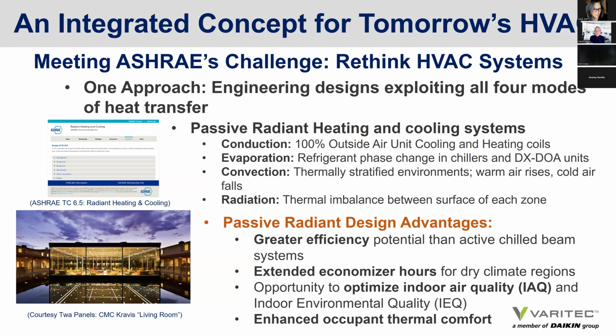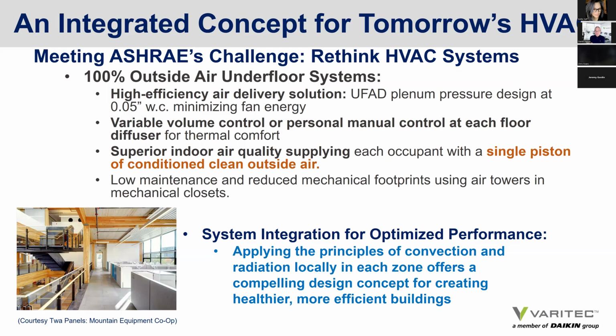Also to look at 100% outside air passive radiant systems because of outside air delivery solutions being more efficient for reasons expressed. Variable air volume control or personal manual control is available at each floor diffuser. Superior indoor air quality, low maintenance, reduced mechanical footprints, and basically an integrated system for optimized performance by applying the principles of convection and radiation locally in each zone, offering a compelling design concept for creating healthier, more efficient buildings. So 100% outside air, underfloor, radiant cooling and heating systems is a design concept that is perfectly doable today. Each system has been proven and vetted out to be effective. And if we bring them together, they can offer arguably one of the most efficient systems in the industry today that optimize indoor air quality.